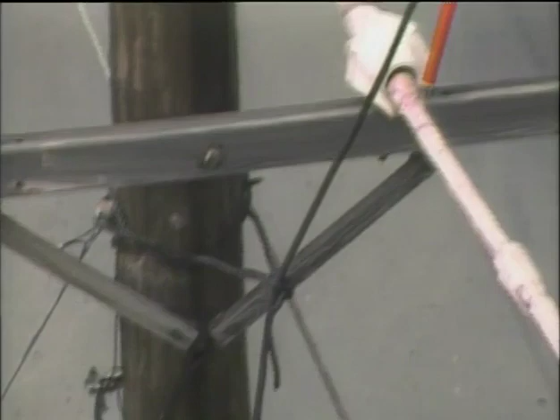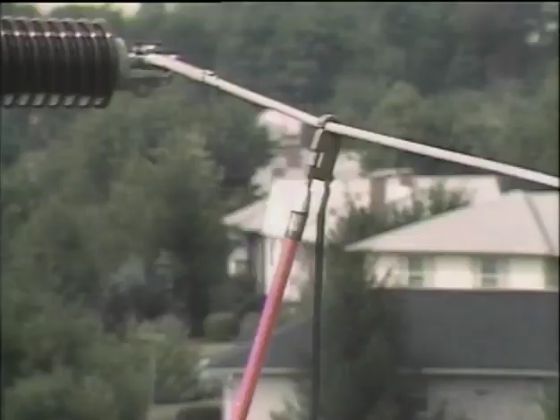When using a temporary ground on circuit lines, it's important to connect the jumper to an established ground before connecting it to a line. If you connect it to one of the circuit lines first, and the line became energized before you got a chance to connect the jumper to ground, you could receive a shock. For the same reason, you want to connect jumpers to the lines that are already grounded before you attach the jumpers to the other conductor lines. Once the circuit has been switched out, tagged, tested for dead, and grounded, the repair work can be done. You no longer need to worry about the lines becoming energized accidentally while you're working on them. When the job's completed, the grounds should be removed in the reverse order, the outside lines being disconnected first. The idea is to maintain a path to ground throughout the procedure.